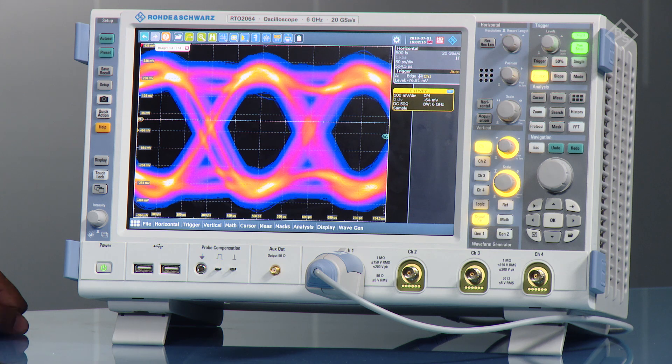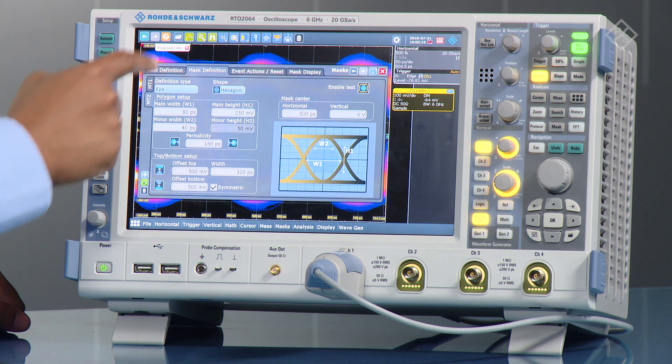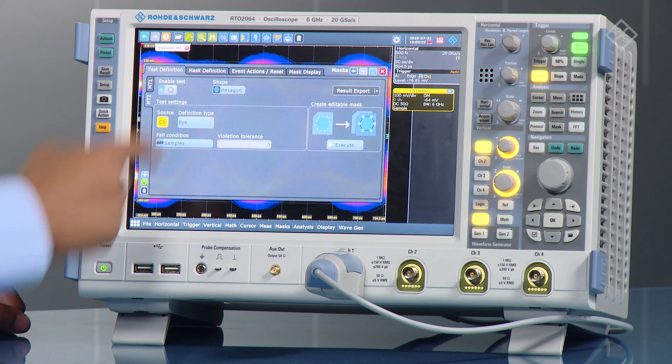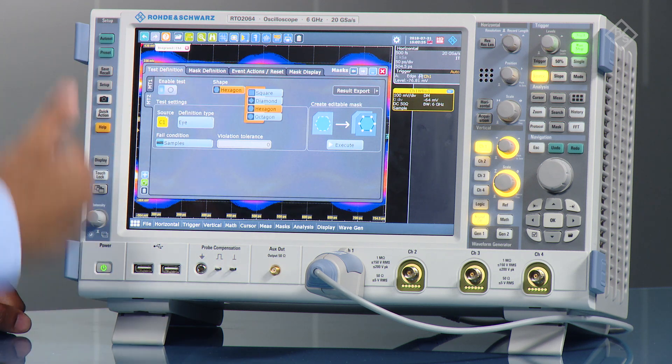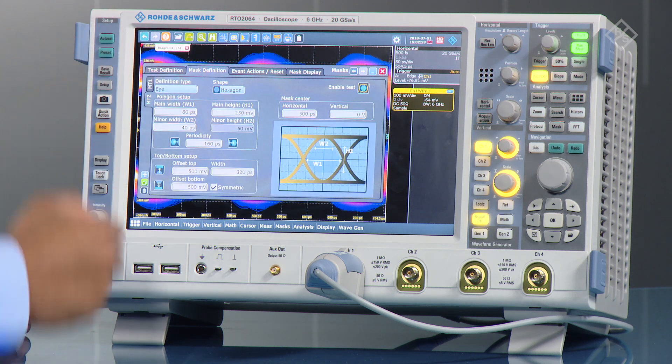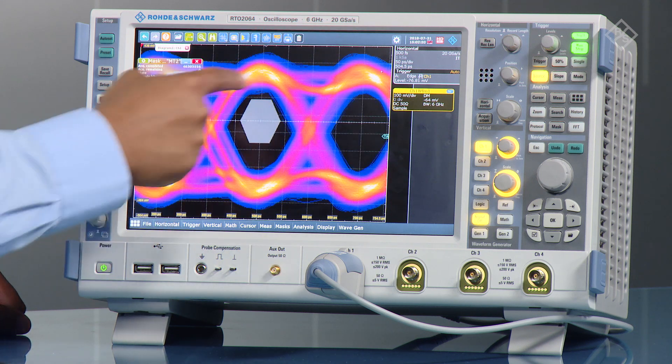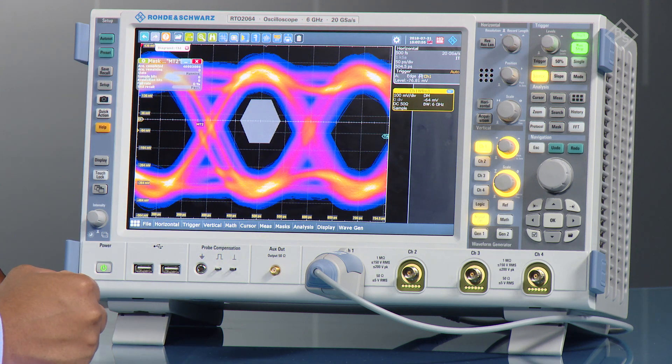Now to set up a mask, you have the mask tool here, and under the test definition you can define what kind of shape you want depending on the standards—either a square, diamond, or hexagon. For this example I've set up a hexagon, and I can just enable the test. In the background you see this is already predefined, and I can set that up.